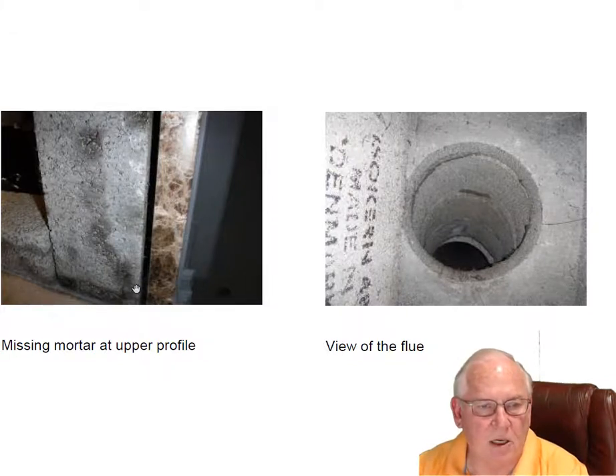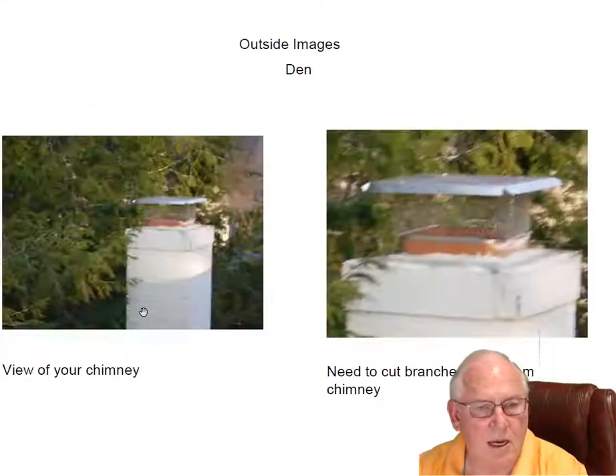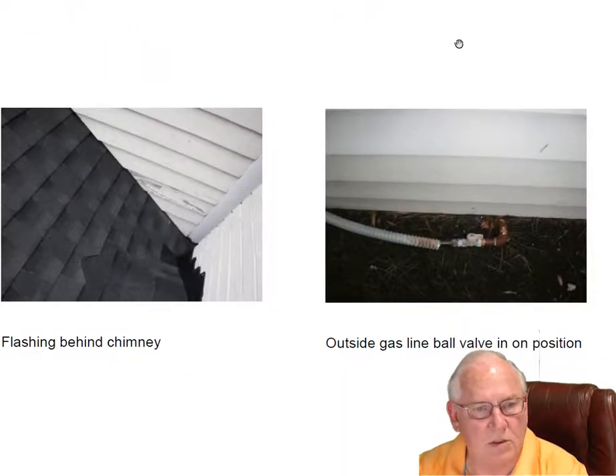Here's that other profile — this is the upper profile that needs to be filled just like in the other room. The Isokern flue system looks great, no problems there. Let's go up on top. Need to cut these branches away — that could be a fire hazard. Also when the wind kicks up, it'll knock the cap loose and eventually that cap will come blowing down.